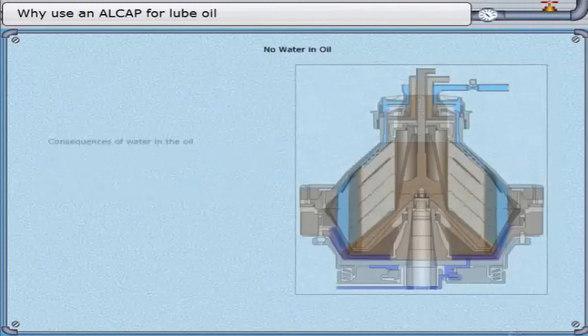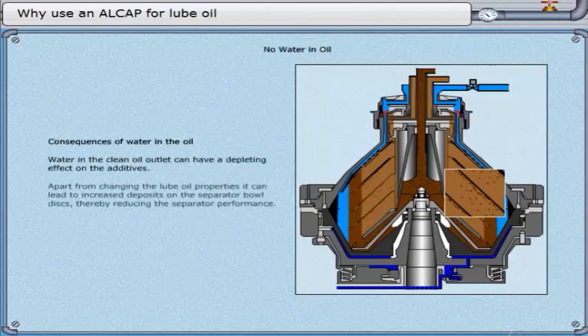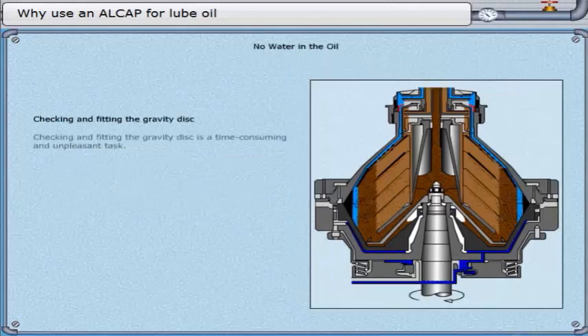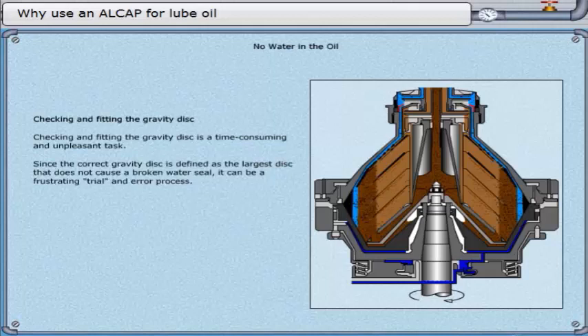Water in the clean oil outlet can have a depleting effect on the additives. Apart from changing the lube oil properties, it can lead to increased deposits on the separator bowl disks, thereby reducing separator performance. Checking and fitting the gravity disk is a time-consuming and unpleasant task. Since the correct gravity disk is defined as the largest disk that does not cause a broken water seal, it can be a frustrating trial-and-error process, and alarms for broken water seals can be frequent.